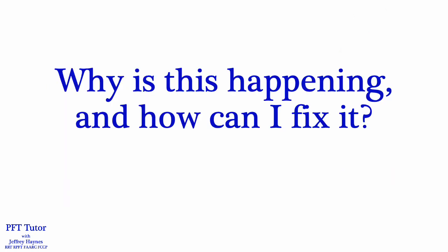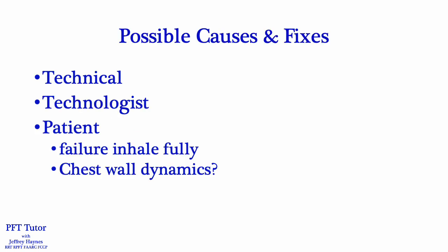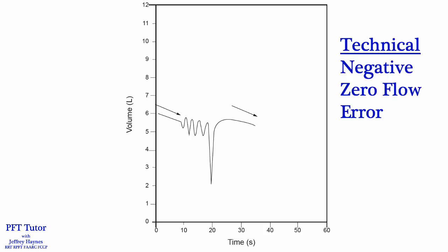So let's talk about why this is happening and what we can do to fix this problem. There are a number of reasons why you may encounter submaximal inhalation error during spirometry testing. They can be technical, they can be due to the performance of the technologist, and they can be due to the patient, either failing to inhale fully or possibly chest wall dynamics.